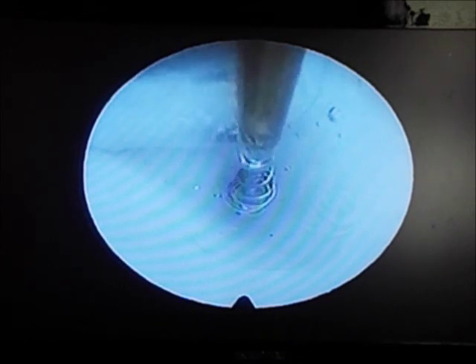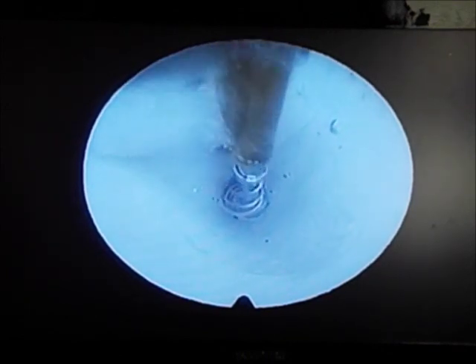Once the outer coil is fully expanded, you begin rotating the handle counterclockwise 10 full turns to disengage the delivery catheter from the device. Once the disengagement has happened, you gently pull the delivery catheter out of the uterine cavity. At this point, the physician will use the hysteroscope to go in and view the number of coils trailing into the uterus, with ideal placement 3 to 8 coils.